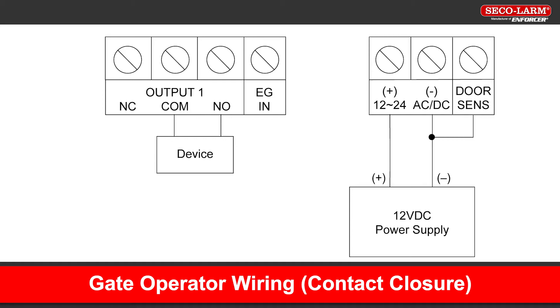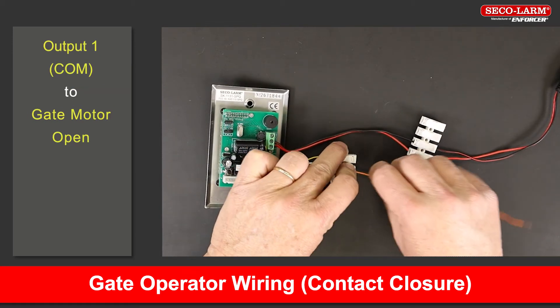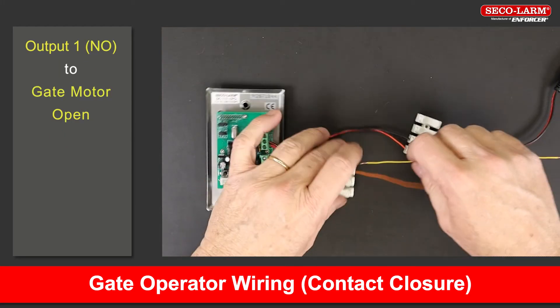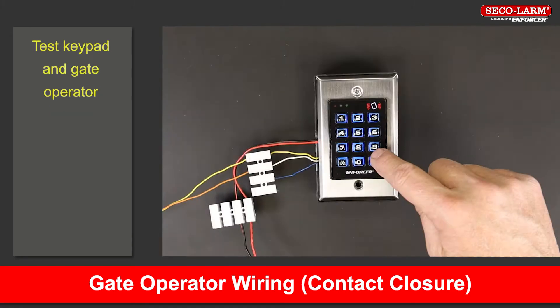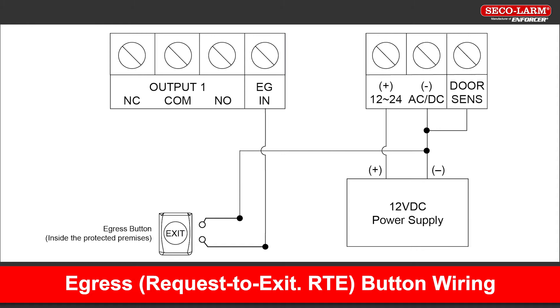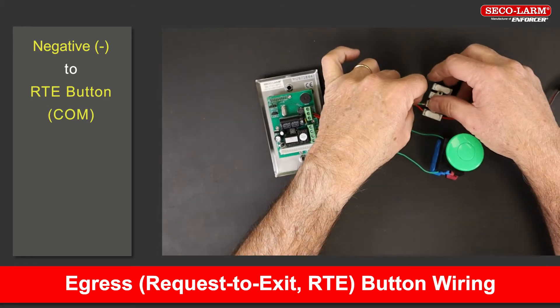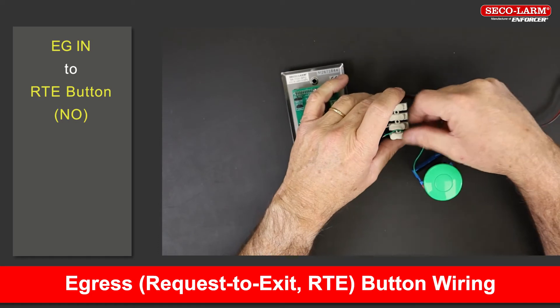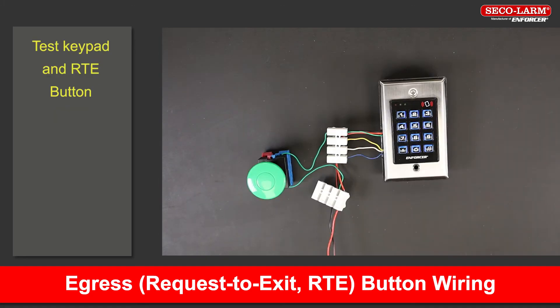Note the wiring diagram here before we show the steps. Connect the positive terminal to the positive of the power supply. Connect the negative terminal to the negative of the power supply. Connect the common of output 1 to the ground of the gate motor. Connect the keypad's EG IN to the request-to-exit button's normally open terminal. Test the wiring to make sure it works.